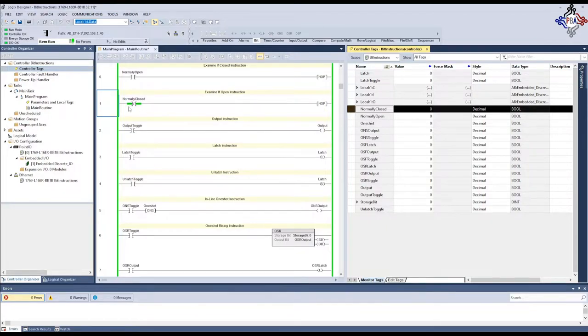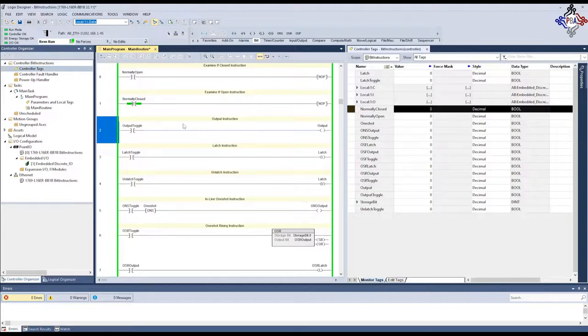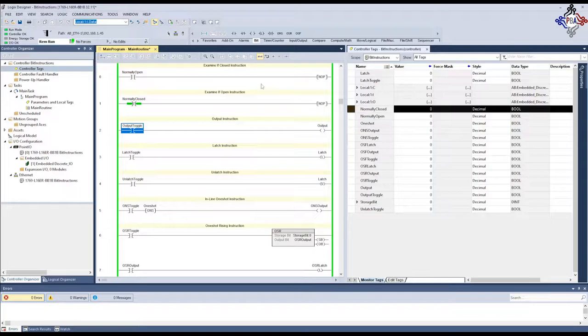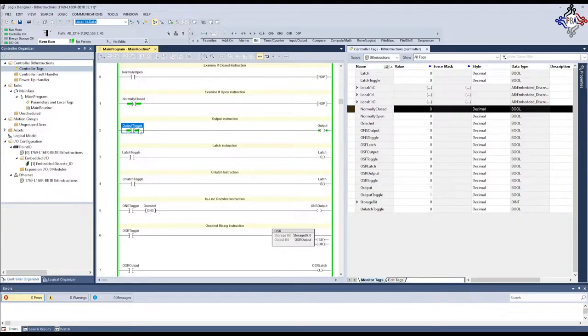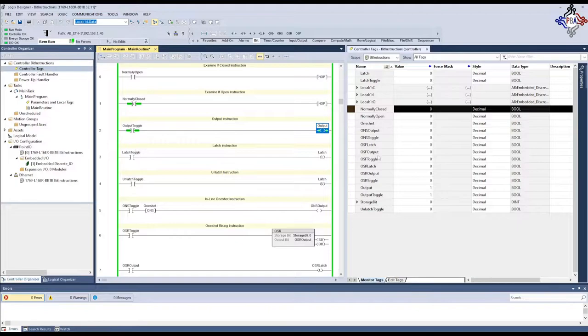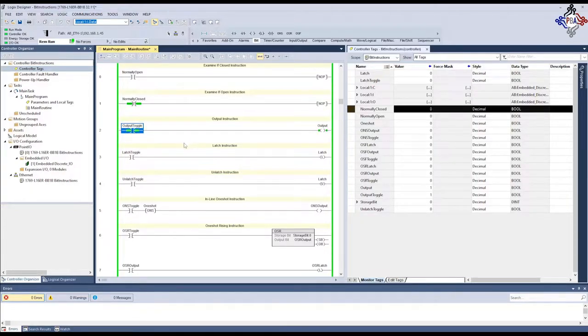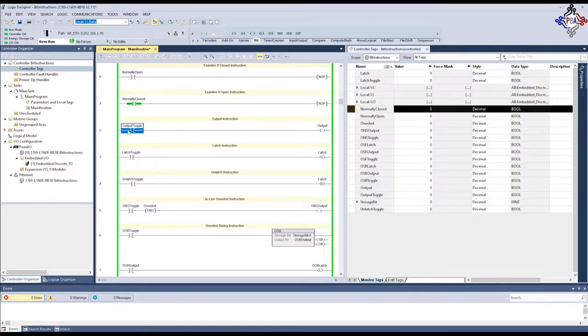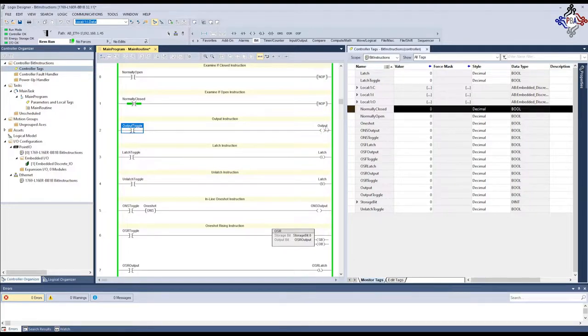Now, moving on to the output toggle. I'm just toggling on and off on this one a regular output bit. The OTE instruction. Output energize. I can also toggle it on from here. If I hit Ctrl T on that tag, you can see that it pops up. And there's our output. I cannot, however, toggle this one on and off because it's being forced on by the controller over here. I can only toggle that input. Now, you can see here when I turn this input on, the output turns on. When I turn this input off, the output turns off. The output instruction is only true, it only turns on when the entire rung is true.